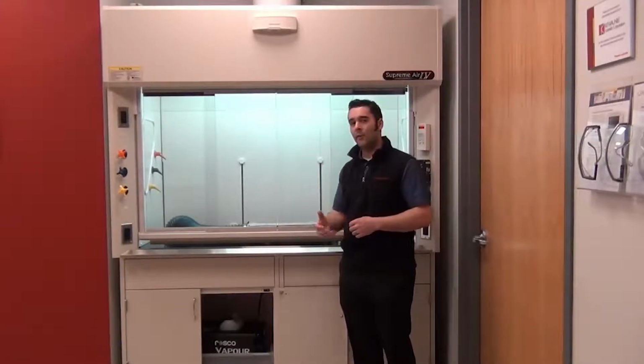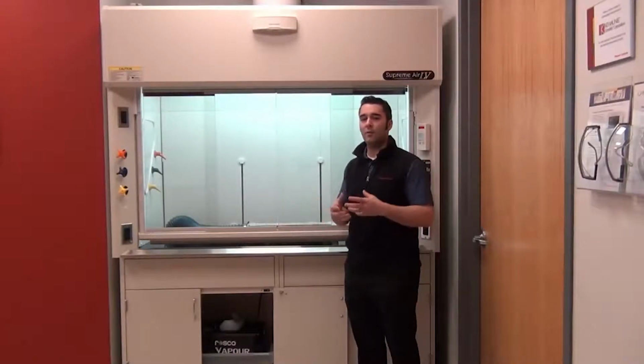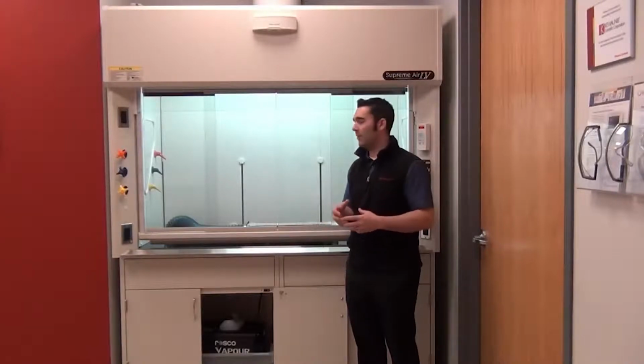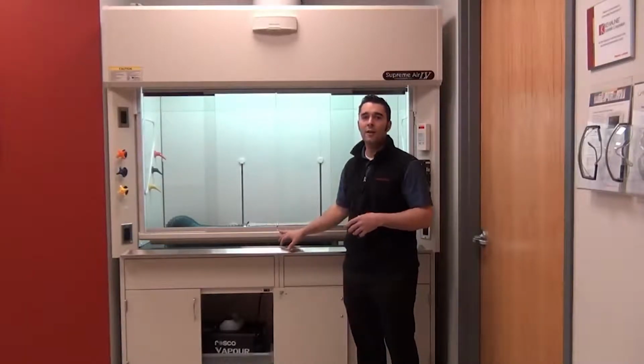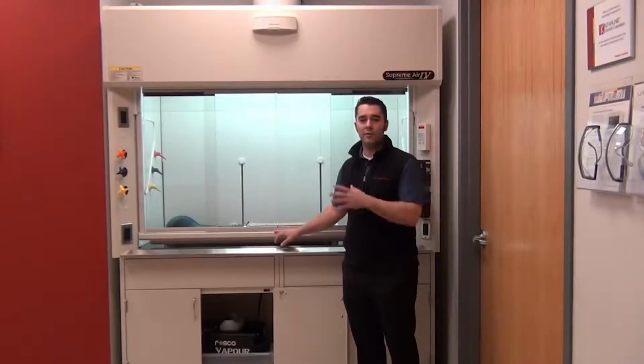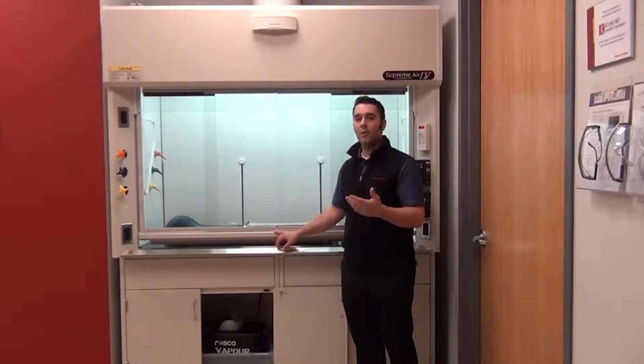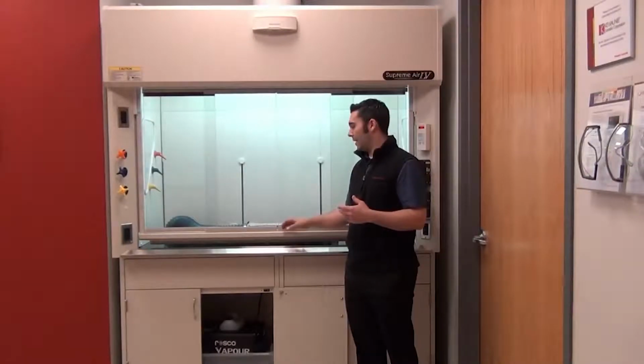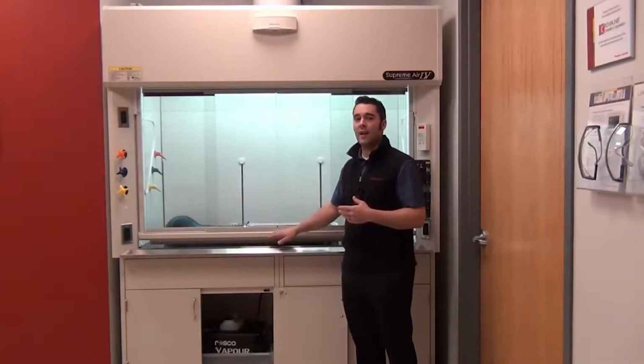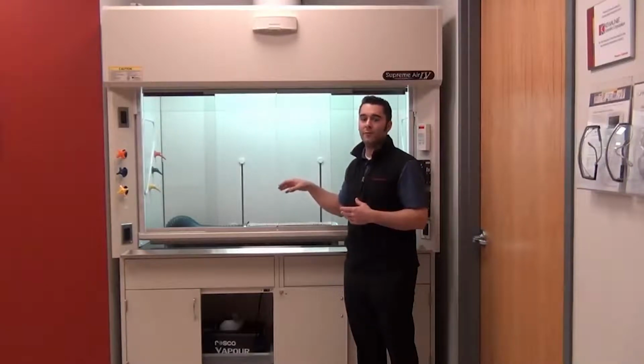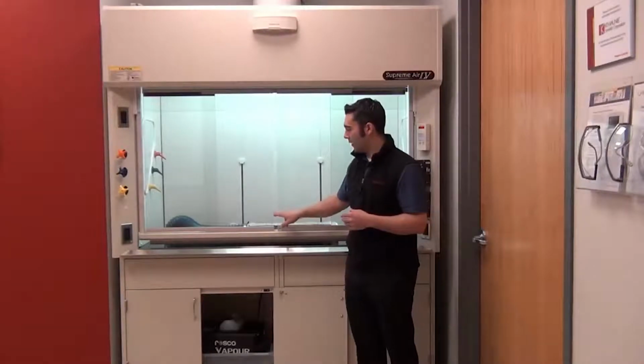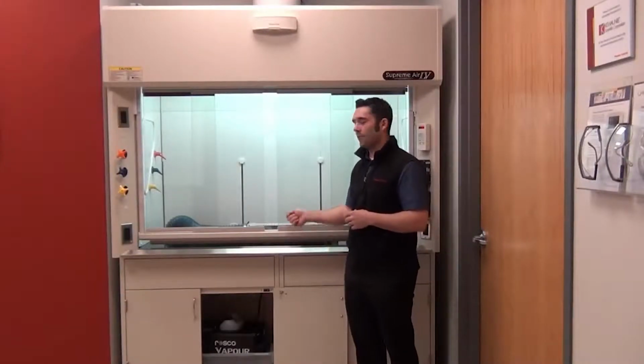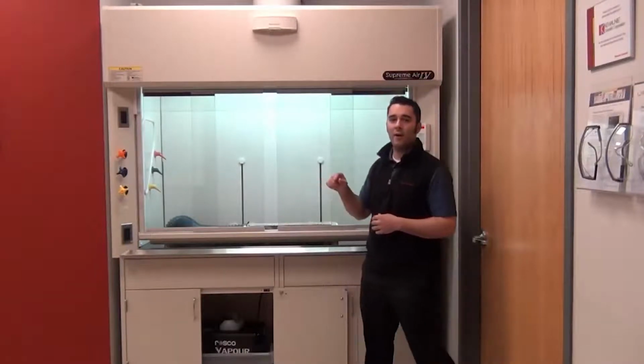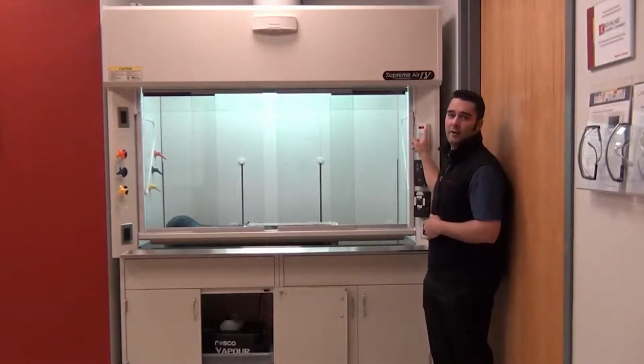So again, in a compounding pharmacy or in a teaching environment, students don't usually get trained, or the personnel inside of the compounding pharmacy may not get trained on the specific equipment they're using. They may have just been told, if I'm using chemicals, I need to have it inside of a fume hood. So what we can do is actually guarantee that no matter what motion you make with this sash, it will take the valve out of its shutoff position, out of its hibernation mode, and put it back to its correct airflow. So if I move any one of these sashes more than 1% or a very small opening, automatically that valve is going to come back into motion, and I'm going to have my 100 feet per minute set point on here again.